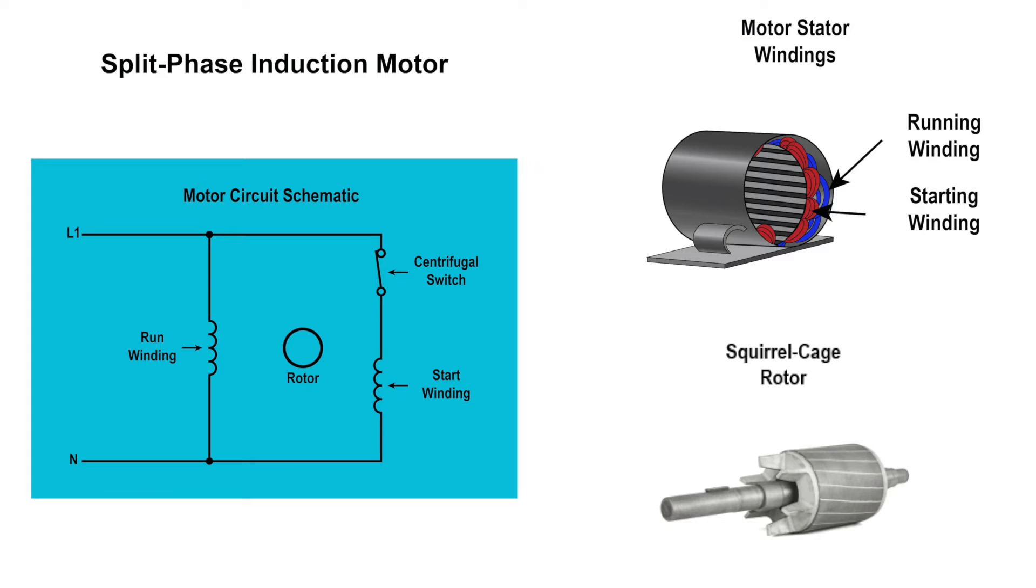The start winding produces a phase difference to start the motor, and when the motor reaches about 75% of its full-rated full-load speed, the start winding is disconnected from the circuit by either a centrifugal switch or electronic solid state switch.